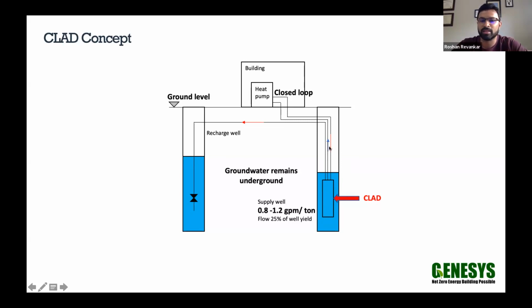On the closed loop side, you can design for your typical 2.5 or 3 GPM per ton as you need, and that's what the CLAD unit is meant to hold. On the open loop side, we only need a flow of 0.8 to 1.2 GPM per ton. So nominally 1 GPM per ton, which the way it's designed is for much lower yield than what the well can actually produce. There are multiple ways to discharge this open loop side of it. It could go into another recharge well or a discharge well, or it could go into surface water, storm water, lake, or whatever. The flow here is very, very nominal. It's about 1 GPM per ton. We've also designed a cracking pressure device, and I'll talk about that a little bit. And that really helps to maintain pressure even on the open loop side, which essentially means you need very low pumping power for this open loop pump.